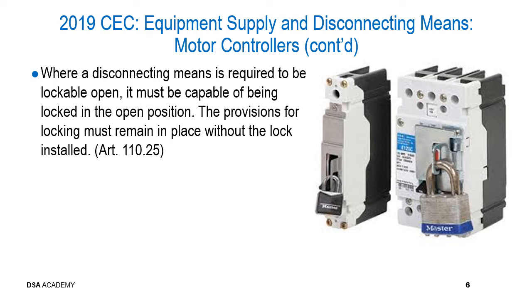And to reiterate what Article 110.25 requires, where a disconnecting means is required to be lockable open, which is what we were just describing as a requirement for the exceptions, it must be capable of being locked in the open position. Additionally, the provisions for locking must remain in place without the lock installed. So the locking provision, the little hasp setup that you see on each of these breakers, has got to be part of the breaker. It can't be a rinky-dink aftermarket weird add-on scabbed-on thing that someone decided was going to be appropriate. That particular hasp lock setup has got to be part of the disconnect itself.